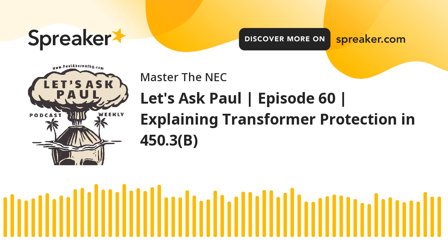So the VA of the transformer divided by the voltage times 1.732. Now, there's values that you can just put into your head that you can just remember. If I'm dealing with a 208-volt secondary three-phase, then I would take 208 times 1.732, and that is 360.25. Now, people like to round, so they say, well, isn't 360.25 really 360.256, so it's 360.26? Okay, if you want to do that, it's not going to change the equation, but go for it if you feel like you need to do that. I will usually only use 360.25 and just stop at two decimal points after. Okay, that's just me. You do you, boo. But that's what I do.